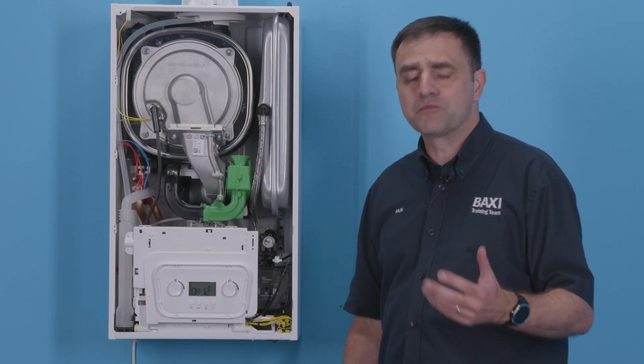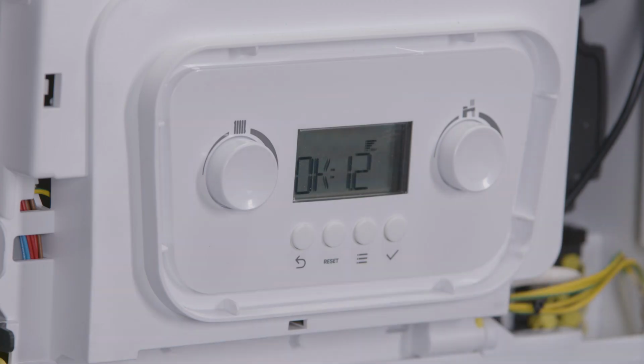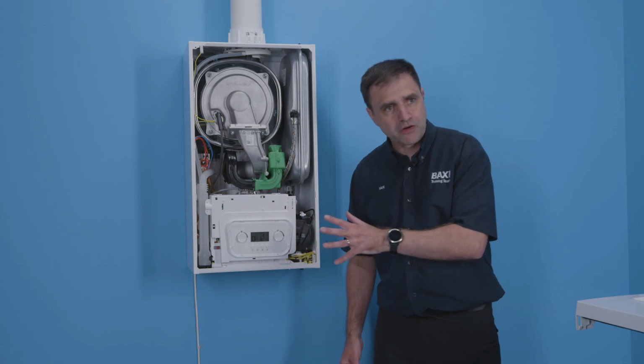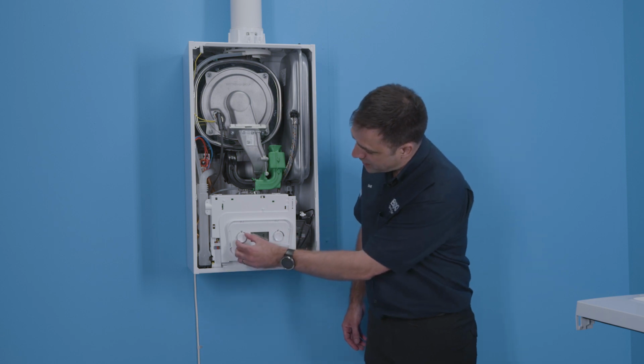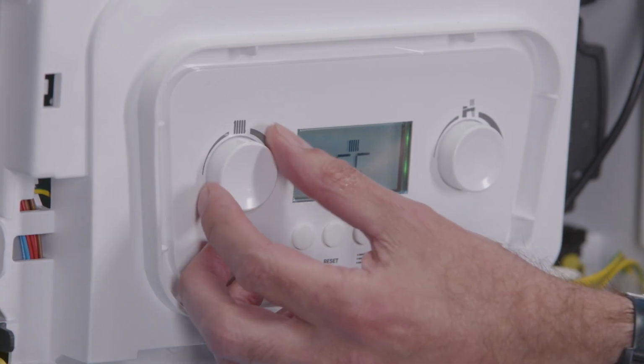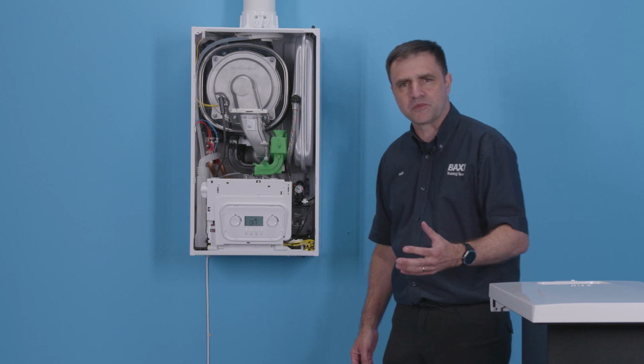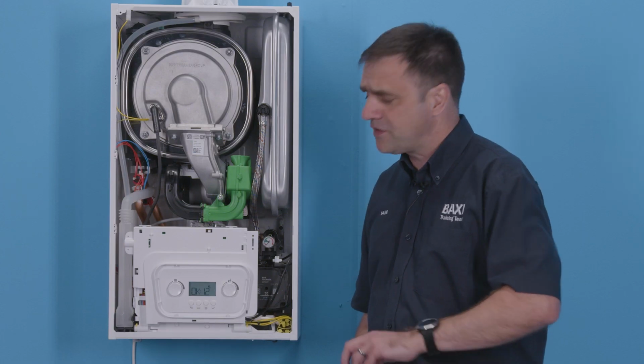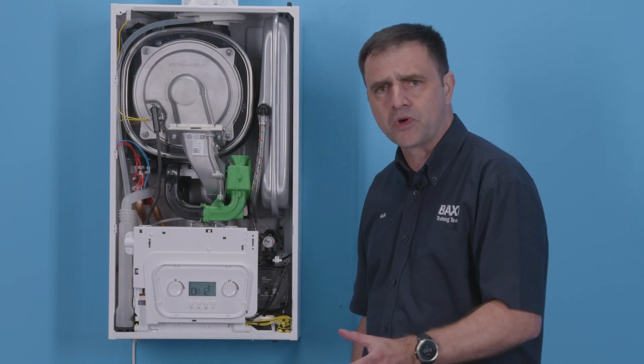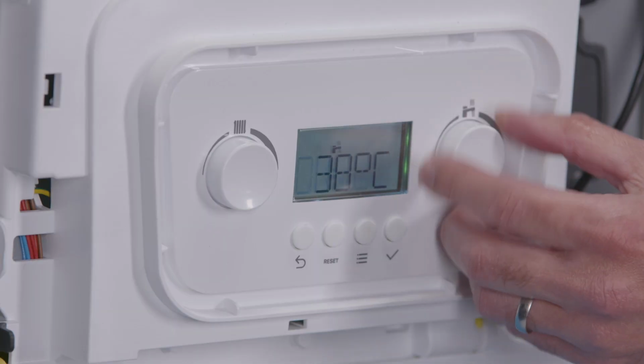So now the deaeration is completed, what you can see on the display is it says OK and the pressure's at 1.2 bar. There's no symbols on here at the moment because I've got the heating off. It's a summer-winter switch, so very easy for the customer to use. If they don't want the heating on in the summer, they can just turn the dial down and the heating will go off. The same for the hot water.